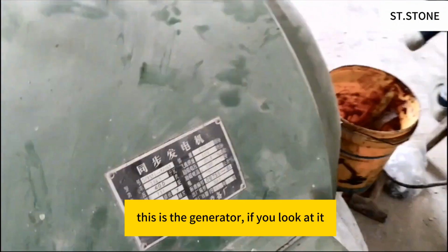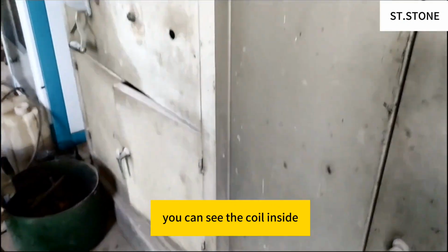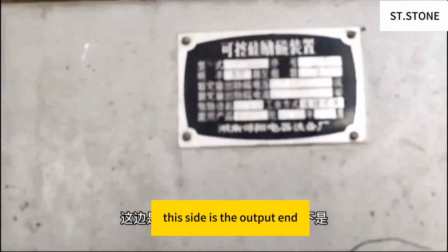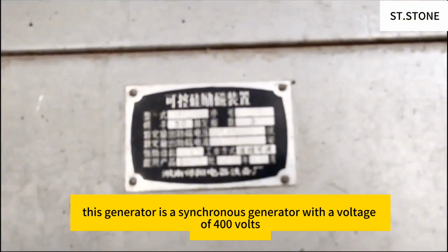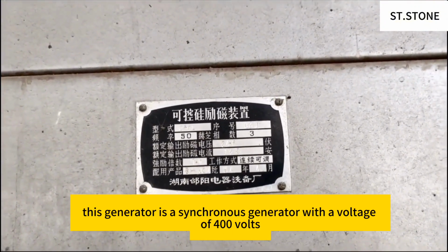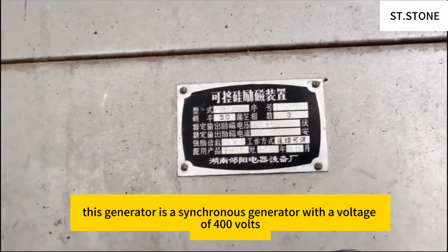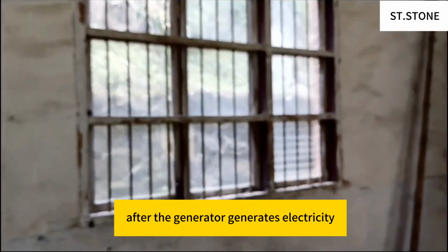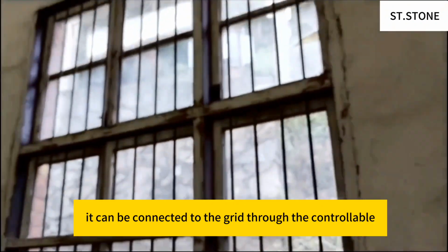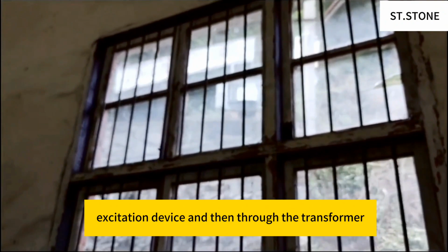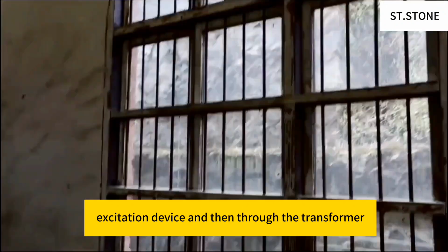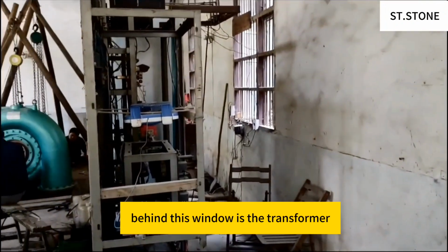This is the generator. If you look at it, you can see the coil inside. This side is the output end. This generator is a synchronous generator with a voltage of 400 volts. After the generator generates electricity, it can be connected to the grid through the controllable excitation device and then through the transformer. Behind this window is the transformer.